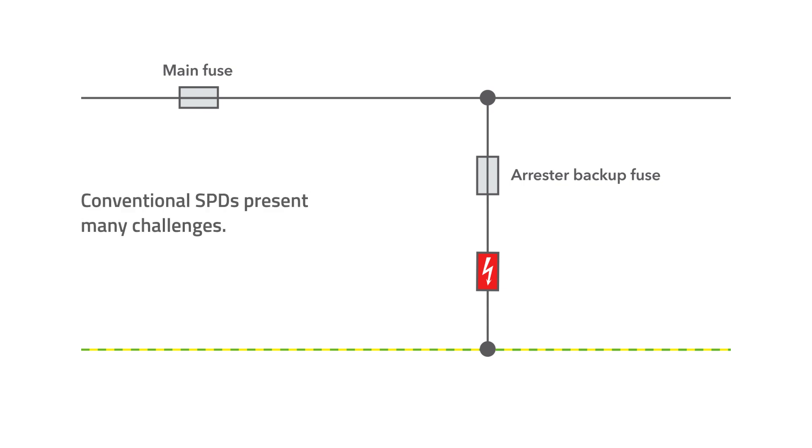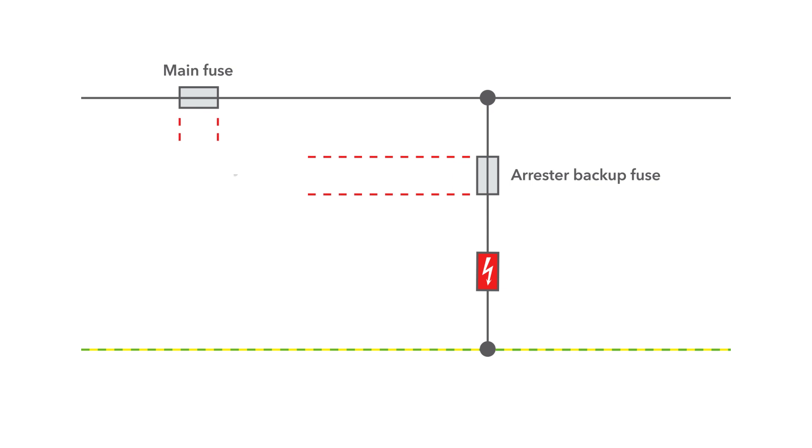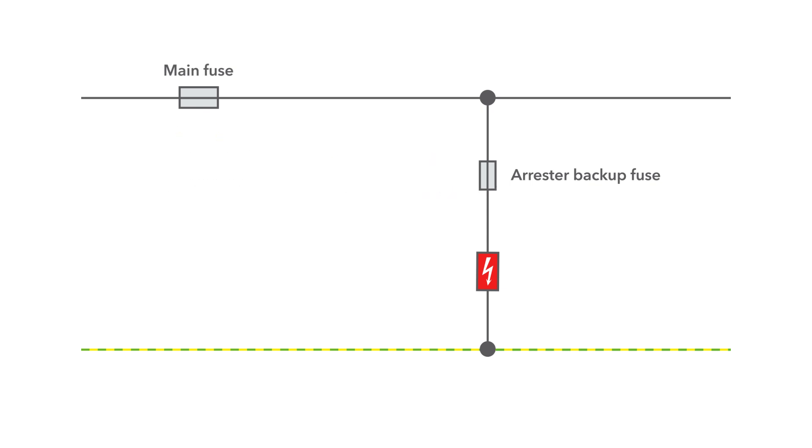With conventional SPDs, the electrical planning engineer is responsible for the backup fuse, and that can be quite tricky. The backup fuse must be correctly dimensioned. If it is too small, it will trip when lightning current flows through it.